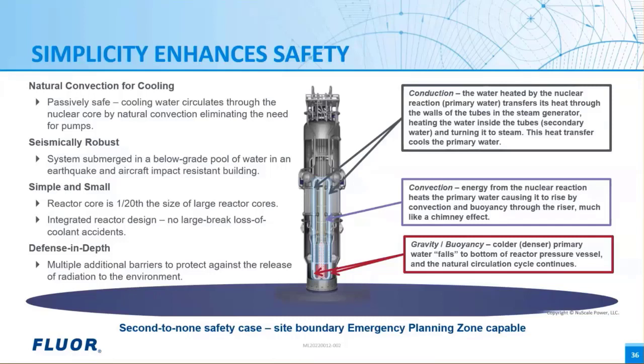The reactors are below grade, submerged in the ultimate heat sink. The cooling water to power ratio of the NuScale SMR is about 4 times higher than a typical pressurized water reactor. It means you have more cooling capability on hand for immediate deployment. The NuScale small modular reactor has a smaller core, so there are fewer fission products in the fuel and thus less decay heat to remove. And as I mentioned, there's almost no possibility of a loss of coolant accident due to a large bore pipe break, since there are no large bore pipes in the NuScale SMR.